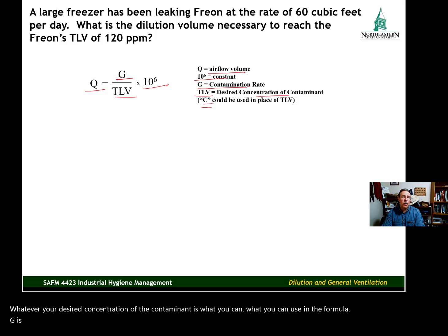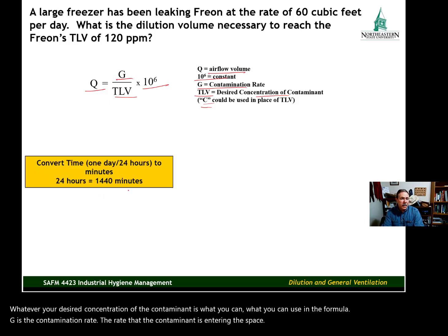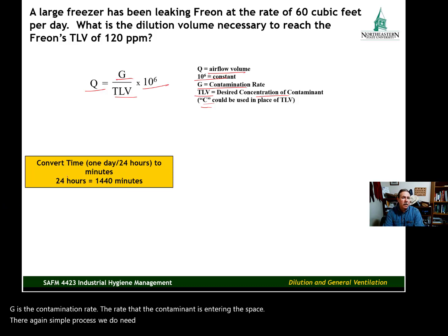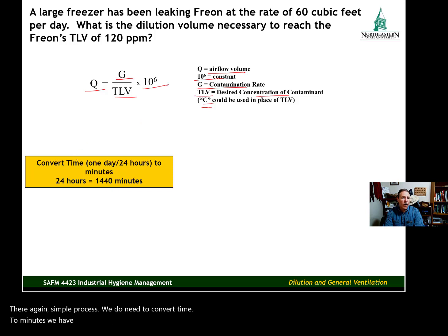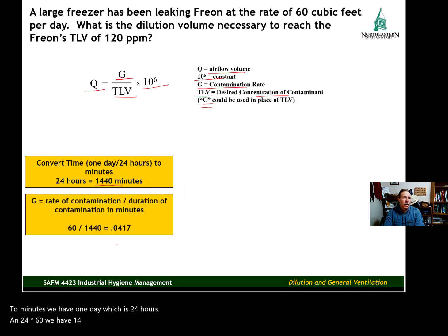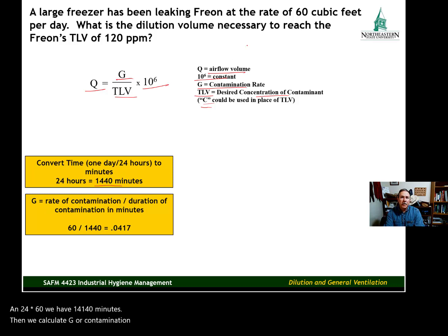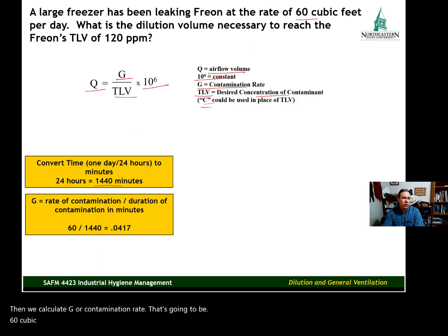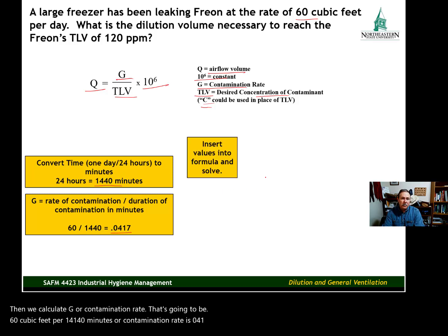G is the contamination rate — the rate that the contaminant is entering the space. We need to convert time to minutes: one day is 24 hours, and 24 times 60 gives us 1,440 minutes. Then we calculate G, our contamination rate: 60 cubic feet divided by 1,440 minutes gives us a contamination rate of 0.0417 cubic feet per minute.